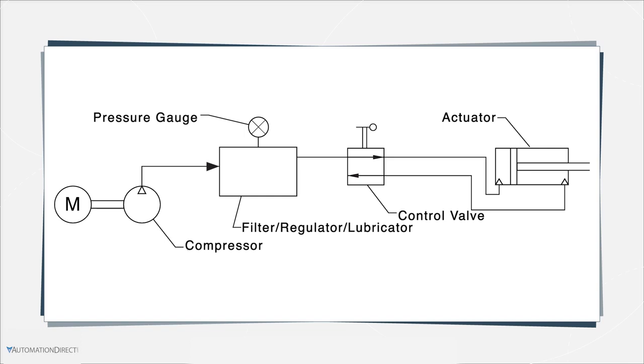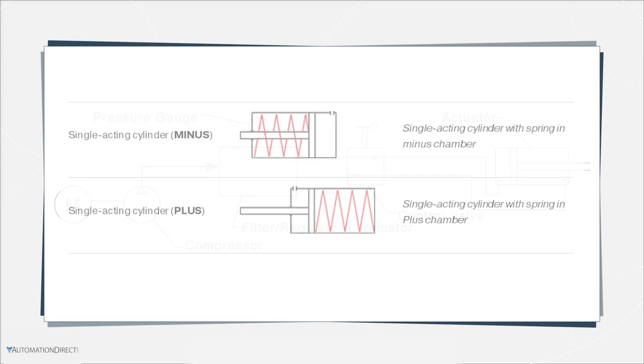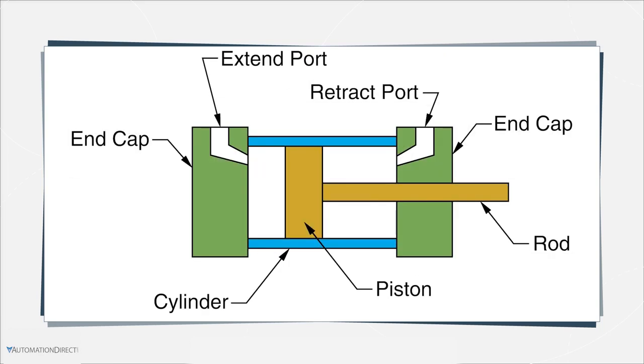This actuator style can be subdivided into two types based on their operating principle: single acting and double acting. Single acting cylinders use one air port to allow compressed air to enter the cylinder to move the piston to the desired position, as well as an internal spring to return it to the home position when the air pressure is removed. Double acting cylinders have an air port at each end and move the piston forward and back by alternating the port that receives the high pressure air.